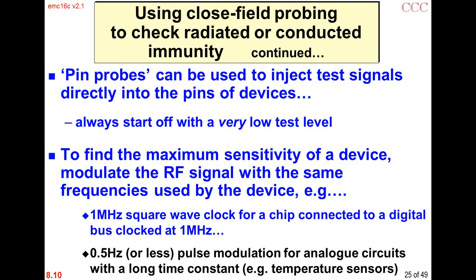But as an RF immunity test, if you waited until you could see a difference in the thermometer reading, it would take at least a minute or two before you saw any difference. So you don't want to dwell at each frequency for a minute, it would take much too long.